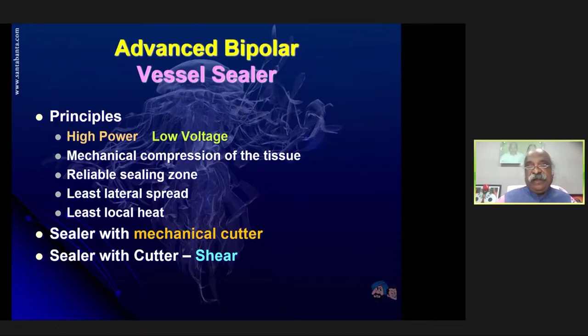The shear is an example where you grasp the tissue with the prongs of the bipolar forceps, either open or laparoscopic, and coagulate it. And at the tip, the current strength is maximum. The density of the current is more. So therefore, you just retract it and place it on the tip. The tip cuts it. That's known as the concept of shear, so that different equipments are not necessary. With the same instrument, you coagulate and cut it with the tip, and that is known as a shear.